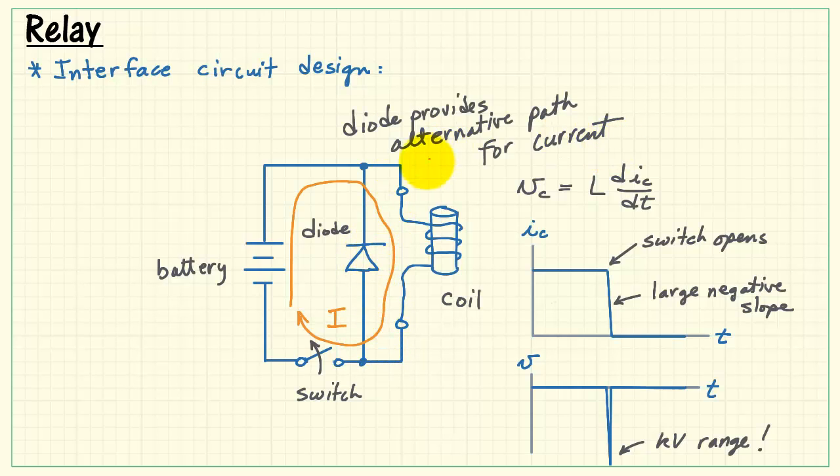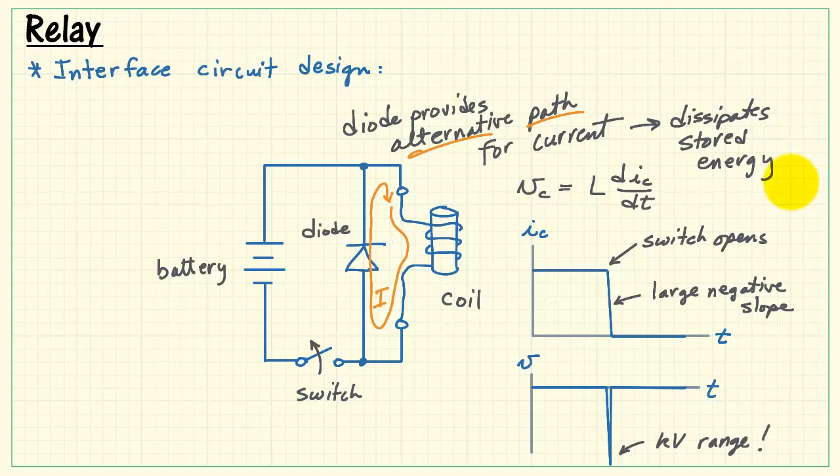But, fortunately, the diode is there, ready to go in the forward bias direction, and it provides an alternative path for the current to flow. That means that the current gets dumped through this diode. That dissipates the stored energy inside the coil, and it protects the switch from arcing.